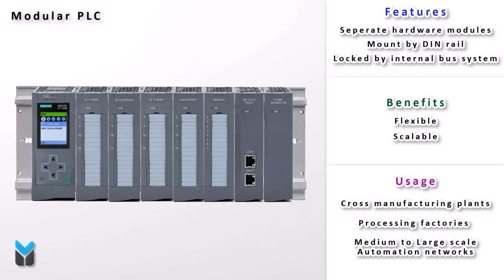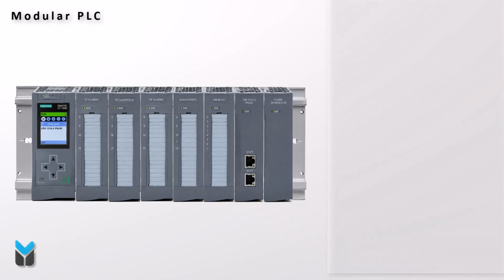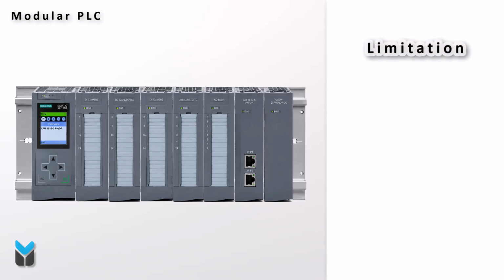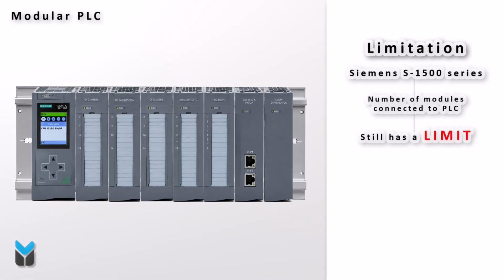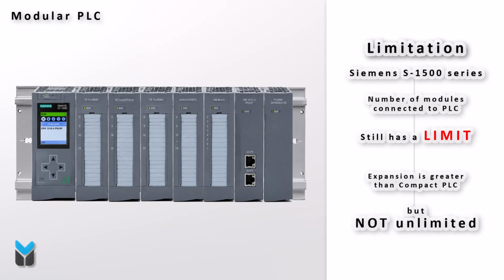Though the expansion capability of a modular PLC is better than that of a compact PLC, it also has certain limitations. For example, a Siemens S7-1500 modular PLC has a limit on the number of modules that can be connected in a single local configuration. Once this limit is reached, additional modules cannot simply be added to the same rack or local configuration.